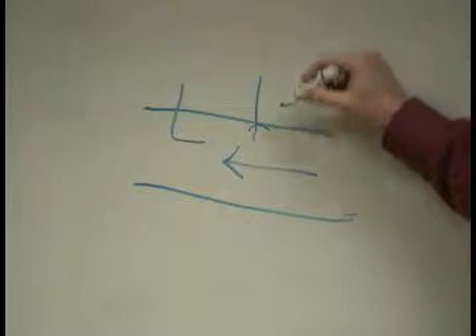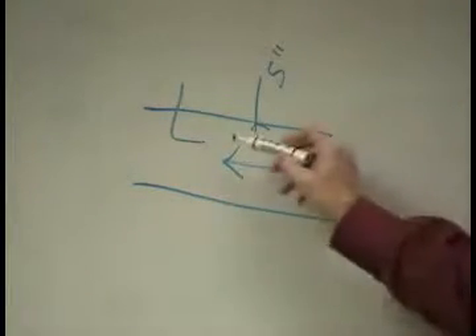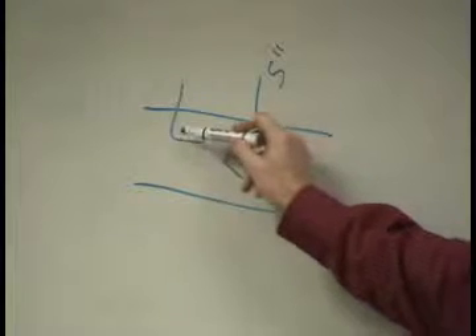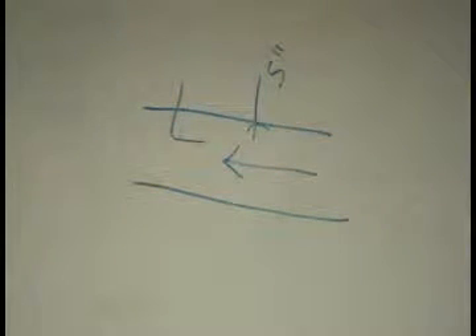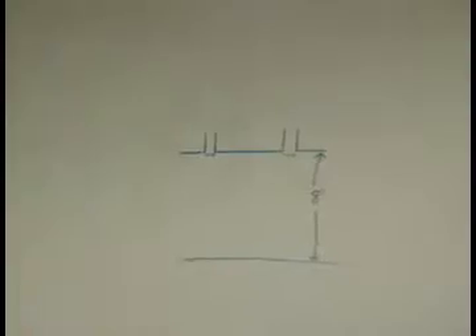So if you had 5 inches of static in your duct and your pressure here, your total pressure was 5.5, your velocity pressure, just the pressure that's the velocity component, is going to be a 1/2 inch. So that's what these pitot tubes are measuring, is what is the velocity pressure. So we've got this thing that measures this velocity pressure. We bring it into our Andover, and then what do we do with it?